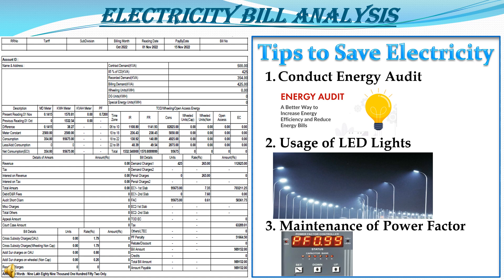Step 3: maintenance of power factor. In our bill, we saw a penalty of around 51,664 rupees due to non-maintenance of power factor. We should use a capacitor bank in our industry to supply reactive energy to the system. In our personal case, there was a flashover in the automatic power factor control (APFC) panel breaker, causing the penalty. The next month we attended the issue and now the power factor is maintained at 0.90 and above, with no further penalty.